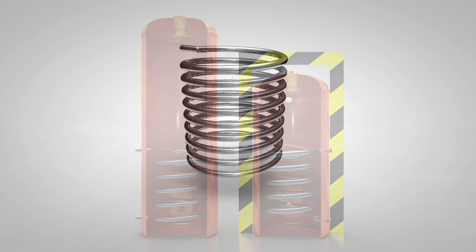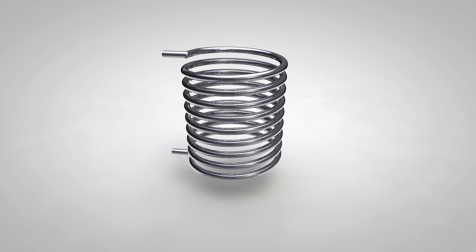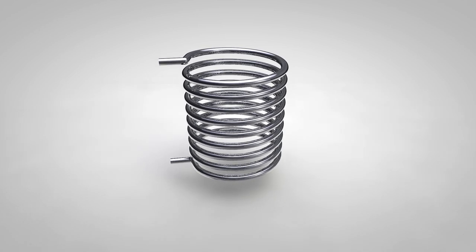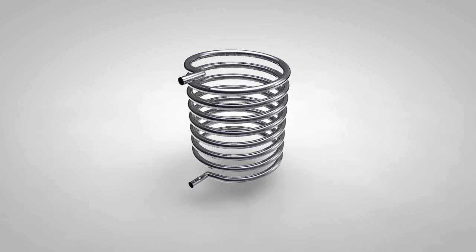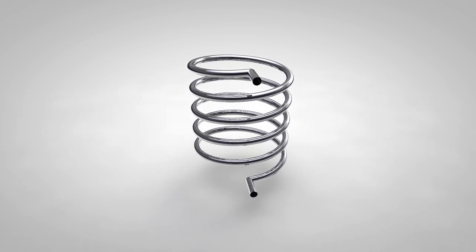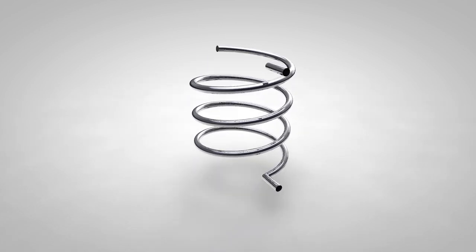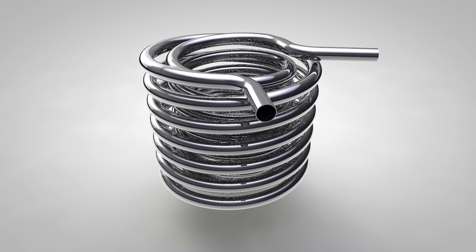Moving on now to the coil design factor, its pitch. The coil pitch determines the application a cylinder can be used on. Although less important now as modern systems use a circulating pump, old gravity feed systems require a coil with a higher pitch so gravity can pull the water through. Gravity feed systems also can't benefit from space-saving coil designs such as coil-in-coil.